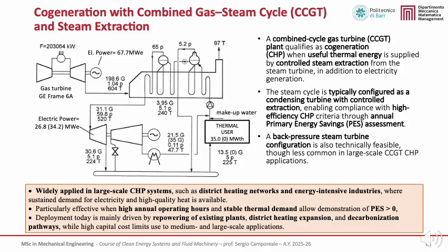Let us now briefly focus on the CCGT scheme shown in the diagram. The system consists of a gas turbine which produces electrical power and discharges high-temperature exhaust gases into the Heat Recovery Steam Generator, or HRSG. Inside the HRSG, thermal energy from the exhaust gases is recovered to generate steam at different pressure and temperature levels, feeding the steam turbine and, at the same time, allowing controlled steam extraction for thermal users. The remaining steam expands through the turbine and is then condensed in the condenser, closing the water-steam cycle with make-up water supplied to compensate for losses.